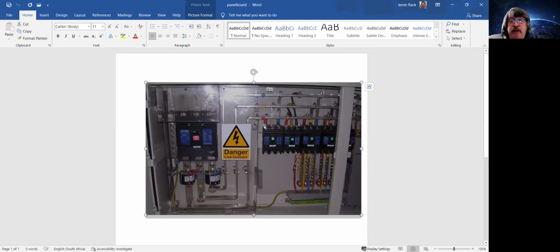As I said, these are 250 amp breakers here, and we can see a bus bar connected here, which would be in line possibly with 250 amps here. And then we've got a wire one connected here, bolted through. Now, this is where the risk could also be. This range would be a 150 to 250 amp product. And so these cables here would be problematic.